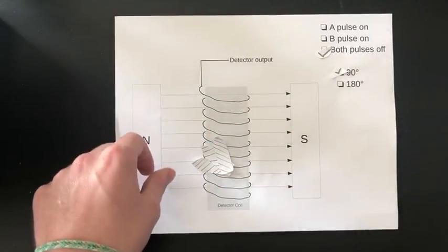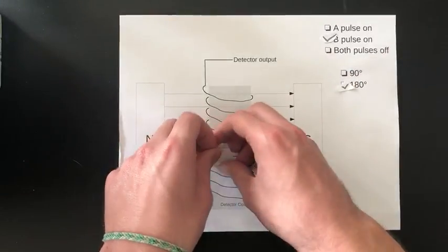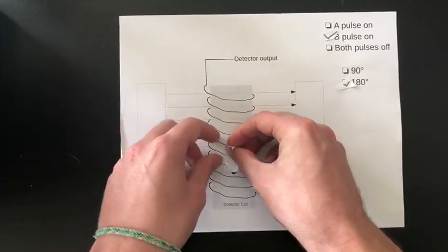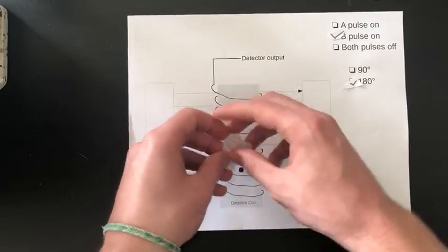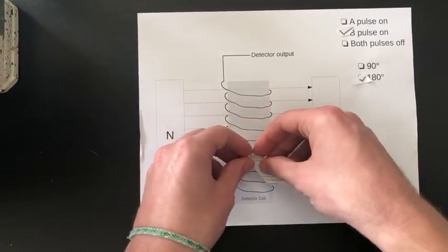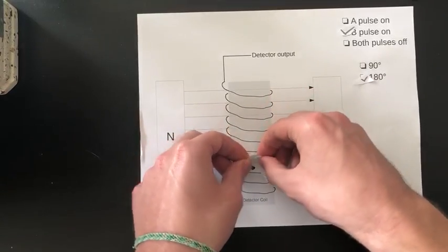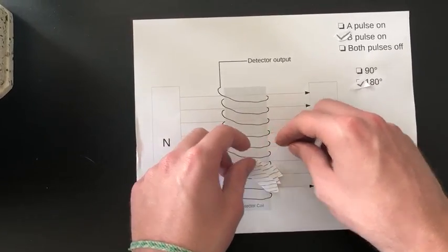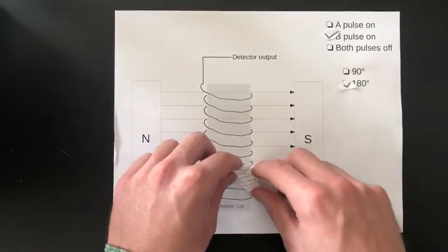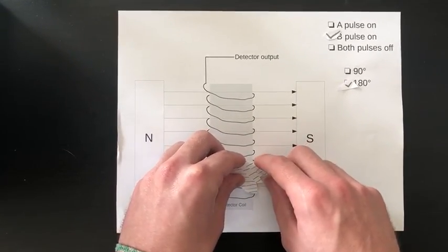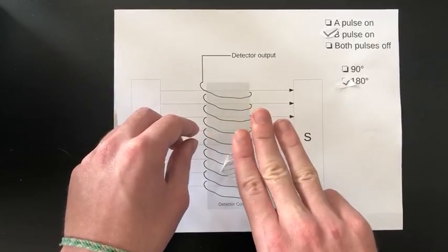And so a way that we can try to correct for this is by activating B pulses of 180 degrees at different intervals. This means that as the protons start to drift down back towards alignment and drift apart, they'll be flipped back over 180 degrees, and they'll be a little bit closer to their previous alignment. However, it's important to note that the magnetization will get lower and lower in amplitude, because when they're flipped 180 degrees, they move closer together again, but they still are a little bit spread.